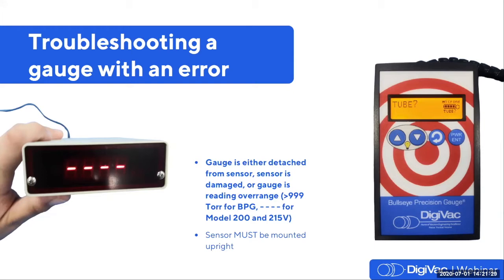This message can sometimes appear if a gauge is powered on at atmospheric pressure and the sensor is laying sideways on a desk. Remember that the sensor needs to be mounted upright always in order to read correct vacuum. If a sensor is lying sideways, possibly suspended upside down on an angle, or basically anything other than straight up and down, the heat generated from the thermocouple filaments will no longer diffuse into the gas correctly as it sort of pulls on one edge of the sensor. This can artificially heat those filaments and skew readings.